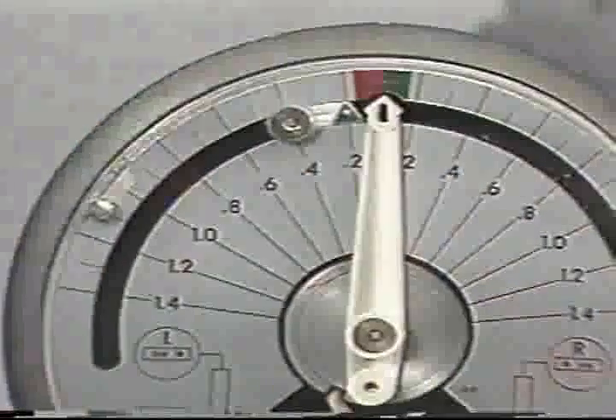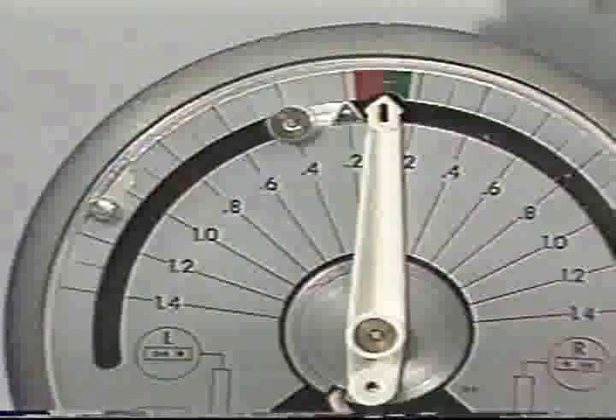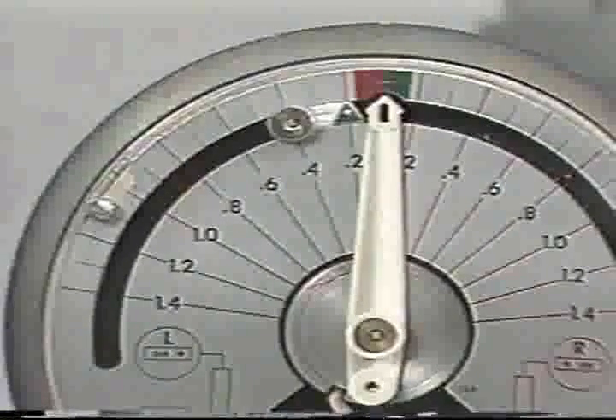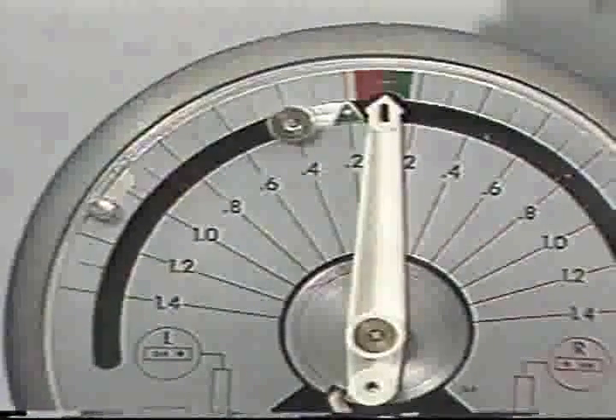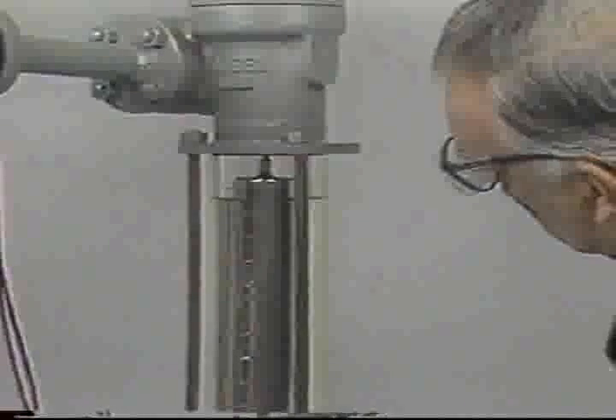In a liquid-liquid interface application, the specific gravity is the difference between the specific gravities of the light and heavy phase. The specific gravity is set on the calibration plate of the transmitter. With the chamber filled completely with the lighter phase, the expected output is 4 milliamps. If the actual value is different, adjust zero until ideal is reached.